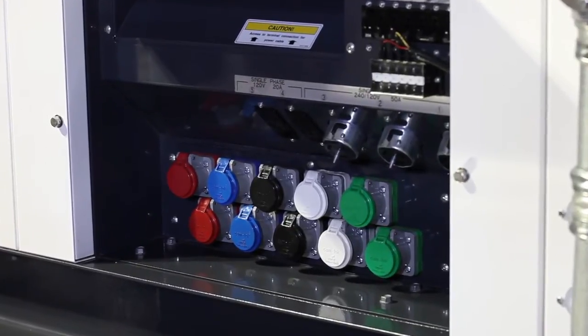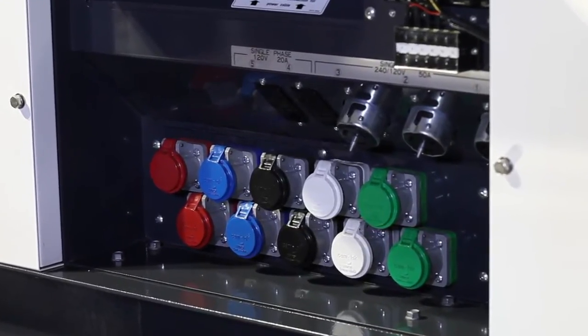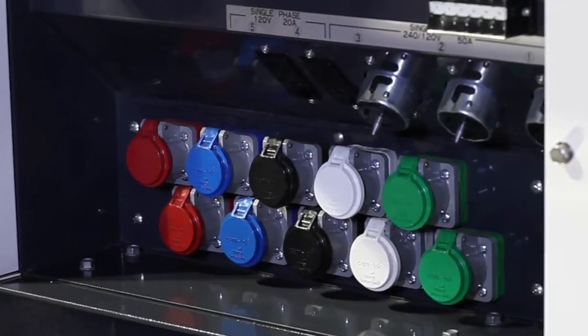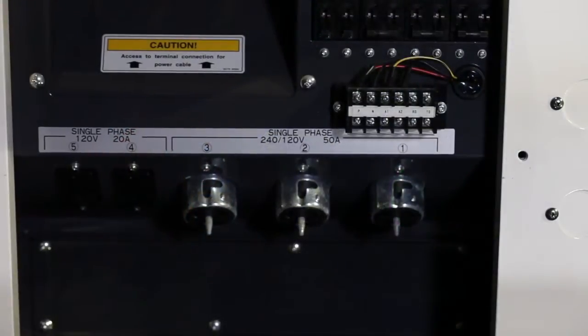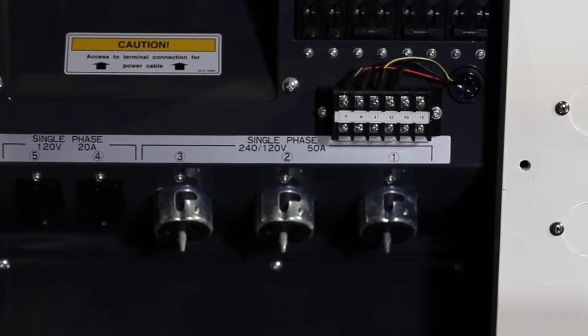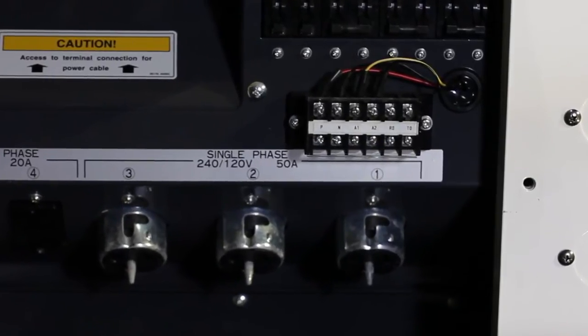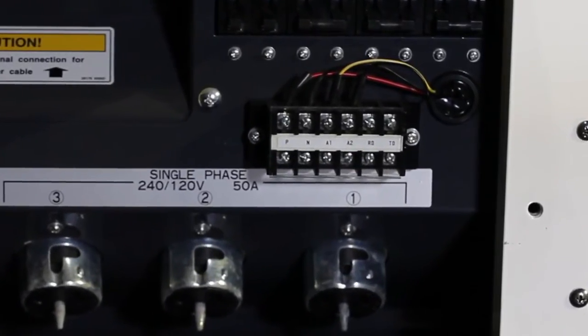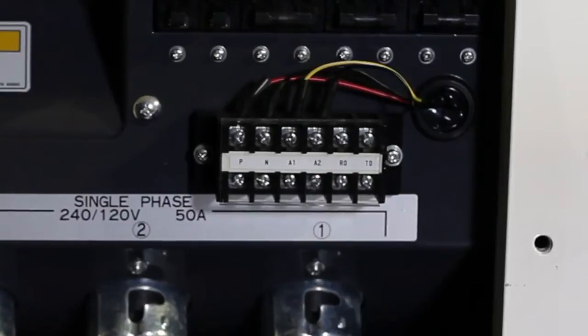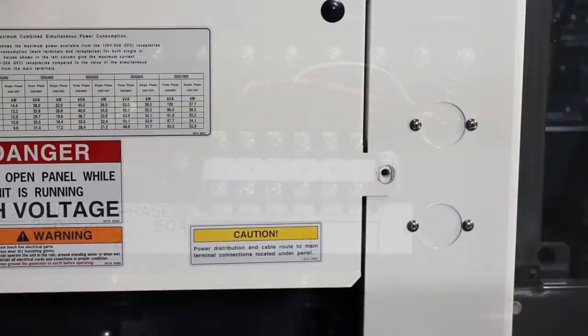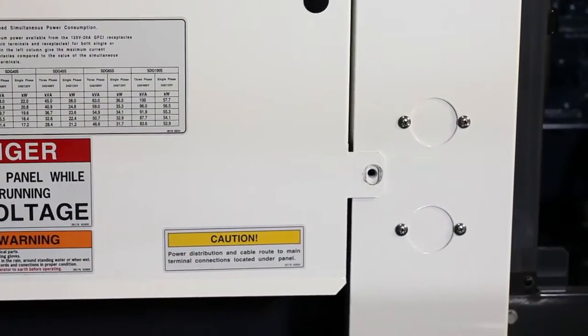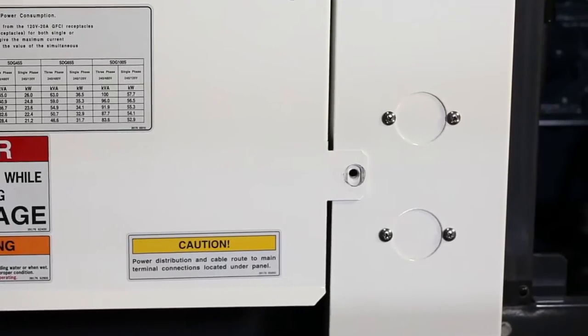As an optional accessory, MMD can install a cam lock panel in the provided knockout panel located below the accessory outlets. All MMD PowerPro generators feature auto start contacts for hookup to auto transfer switches or other means available to remotely start the genset. There are also provisions for other accessories such as external battery chargers and block heaters.